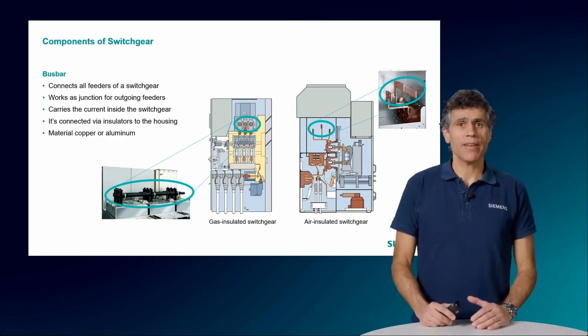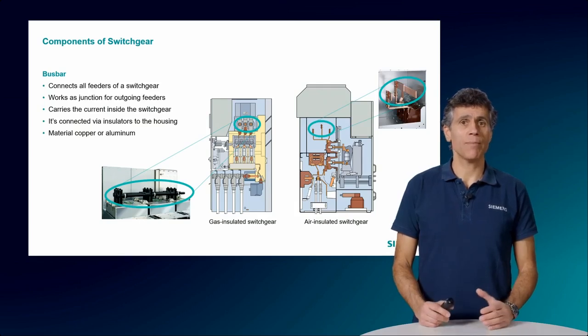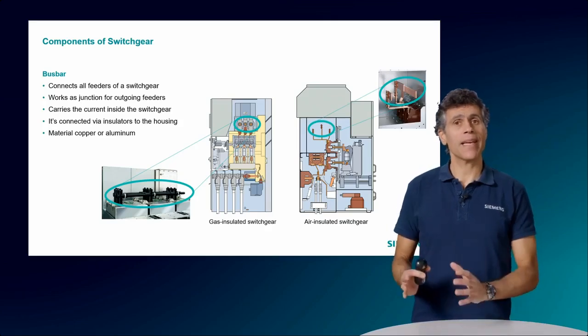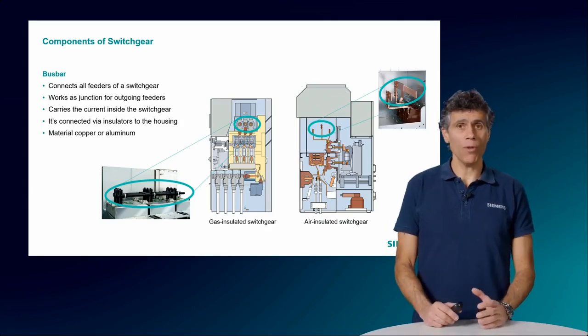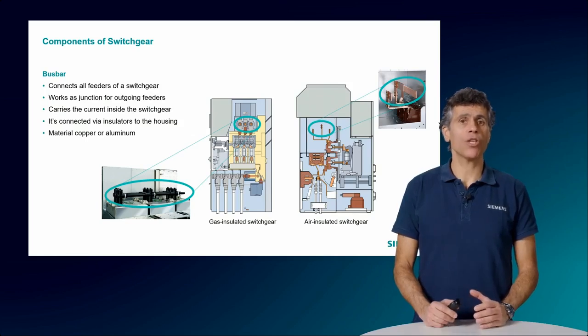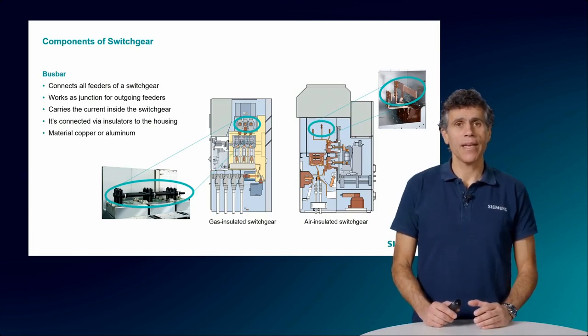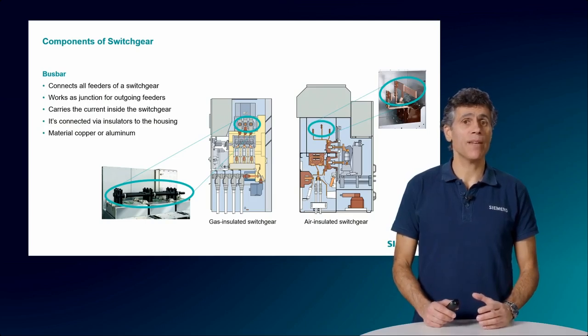Because the busbar carries current, there are two other challenges that it must master, as do most of the components inside the switchgear: the heat and the mechanical strength. In normal operation mode, the busbar gets hot, and this heat must be dissipated so that the temperature inside the switchgear doesn't melt the components, and so that the switchgear enclosure can be touched without causing harm to people. In case of a fault, like a short circuit, the busbar undergoes very high forces.